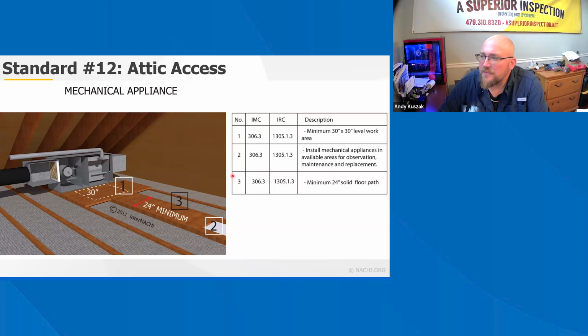mechanical appliance. The passageway should be at least 30 inches high, at least 22 inches wide, and not more than 20 feet in length when measured along the center line of the passageway from the opening to the appliance. There are some exceptions. The passageway flooring should be at least 24 inches wide. A service area is required in front of the mechanical equipment with a minimum dimension of 30 inches by 30 inches.